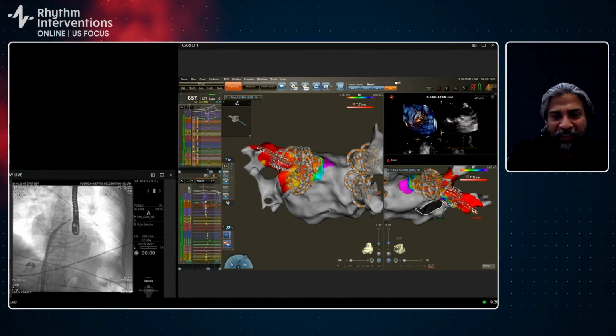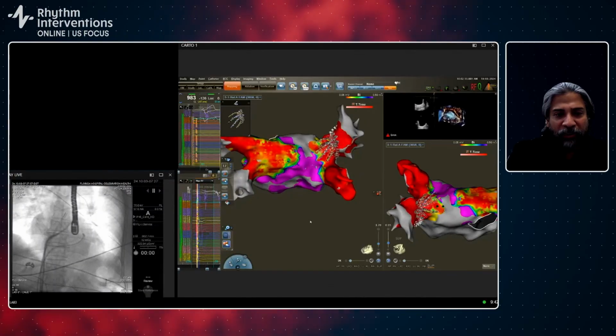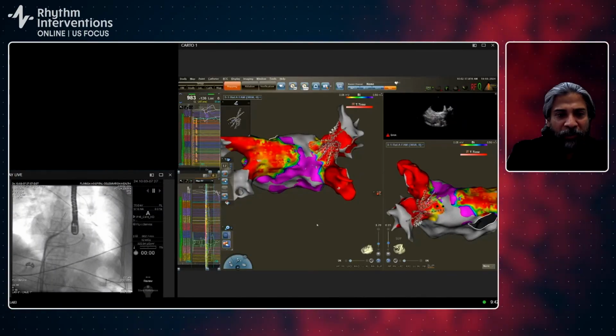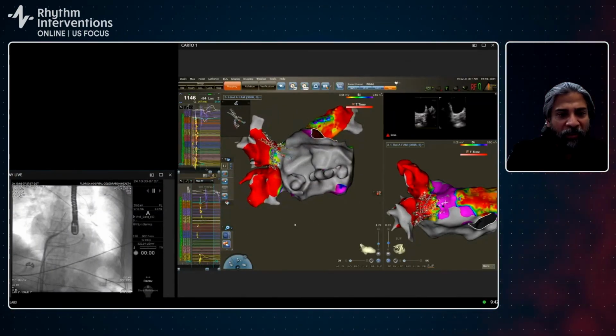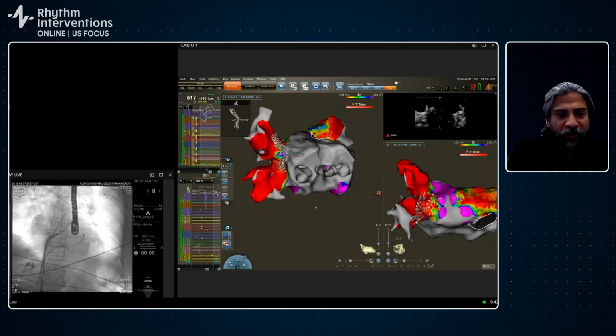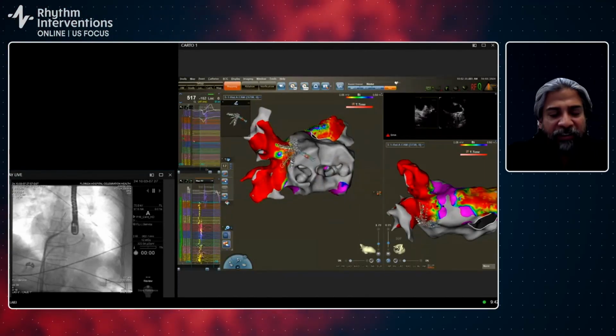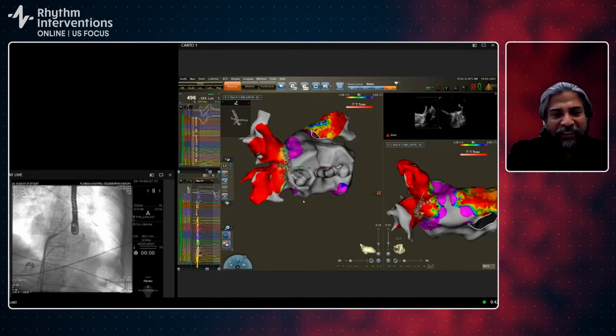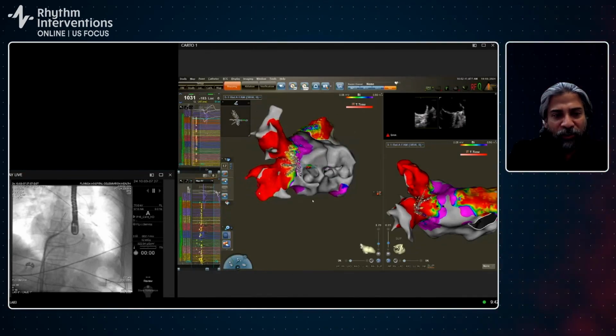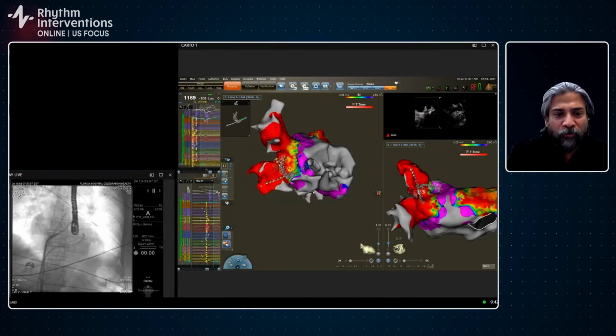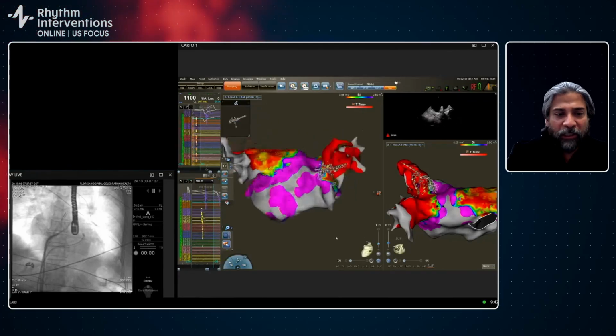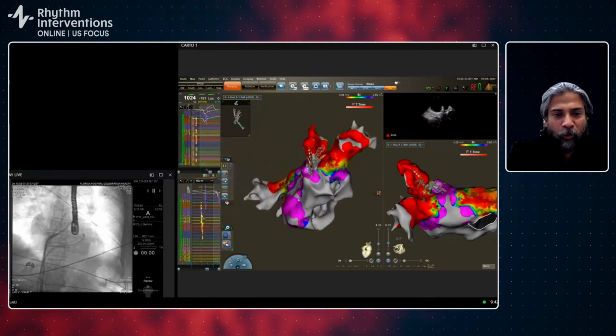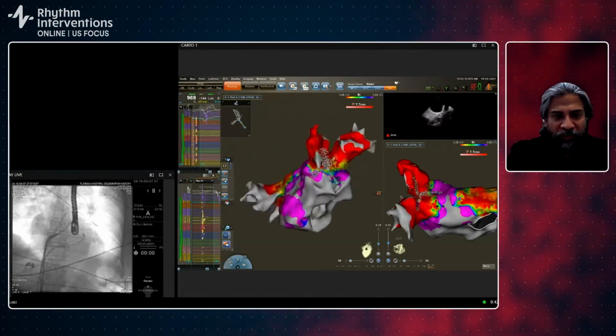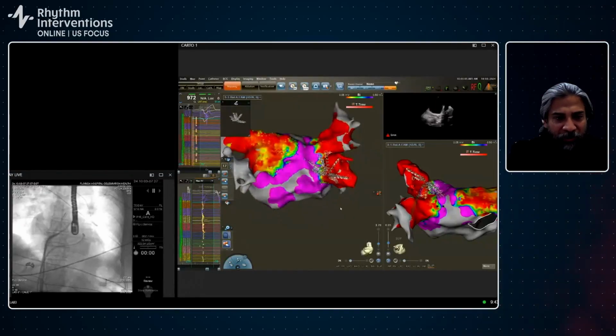You can pace from the Pulse Select catheter too, but I'd like to pace from the OctaRay from all poles to confirm entrance and exit block. I would put it in different areas of the carina, different areas on the roof. One of the things with OctaRay is that the splines are bent. You can tell which area is touching and which area is not touching to confirm that you had good contact when taking those low voltage points and high voltage points. So there's very little chance of mistakes here.